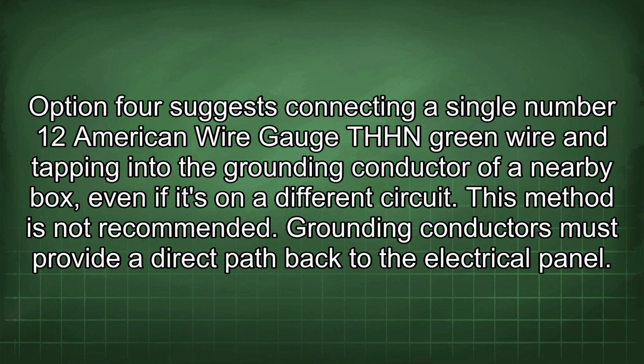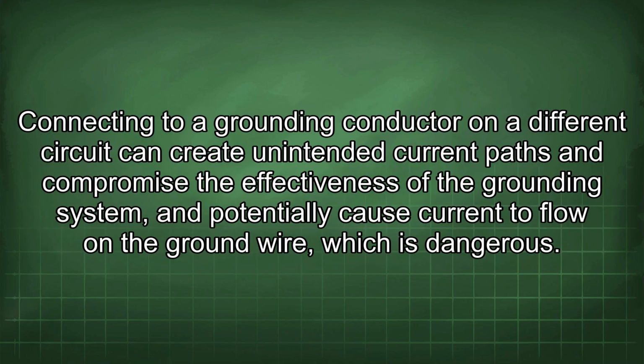Option 4 suggests connecting a single number 12 American wire gauge THHN green wire and tapping into the grounding conductor of a nearby box, even if it's on a different circuit. This method is not recommended. Grounding conductors must provide a direct path back to the electrical panel. Connecting to a grounding conductor on a different circuit can create unintended current paths and compromise the effectiveness of the grounding system, and potentially cause current to flow on the ground wire, which is dangerous.